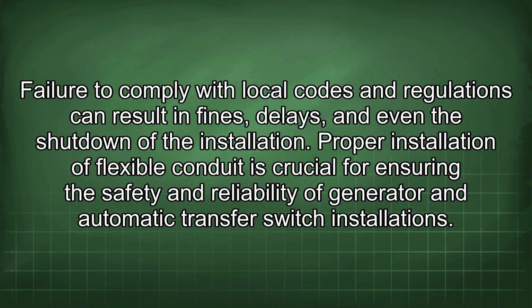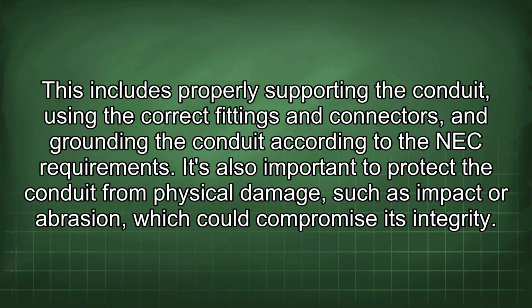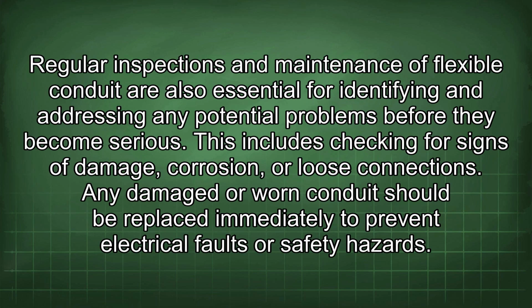Proper installation of flexible conduit is crucial for ensuring the safety and reliability of generator and automatic transfer switch installations. This includes properly supporting the conduit, using the correct fittings and connectors, and grounding the conduit according to the NEC requirements. It's also important to protect the conduit from physical damage, such as impact or abrasion, which could compromise its integrity. Regular inspections and maintenance of flexible conduit are also essential for identifying and addressing any potential problems before they become serious. This includes checking for signs of damage, corrosion, or loose connections. Any damaged or worn conduit should be replaced immediately to prevent electrical faults or safety hazards.